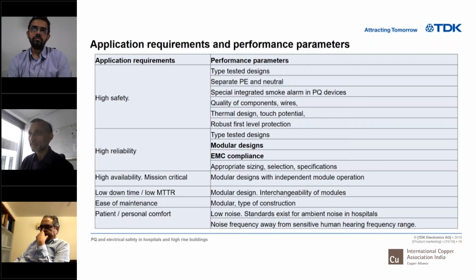The second aspect, apart from safety, is reliability, which is a long-term quality. You should again have a modular design. It should have a very high level of EMC compliance. As I said, in a hospital, we supplied active filters not because they had kVAh billing or a problem with neutral burning or whatever. They had malfunction of patient care equipment, and they really didn't know whether the patient was dying or whether it was an electromagnetic compatibility issue. And then proper sizing, selection and specifications.